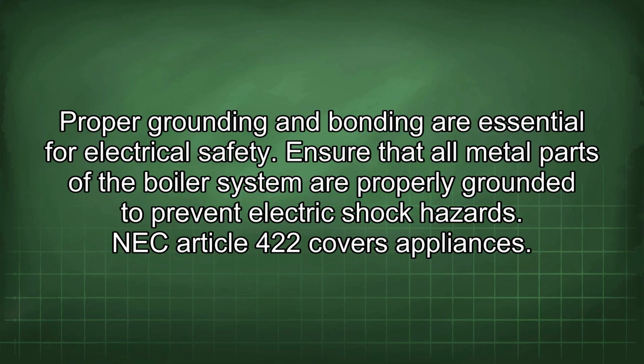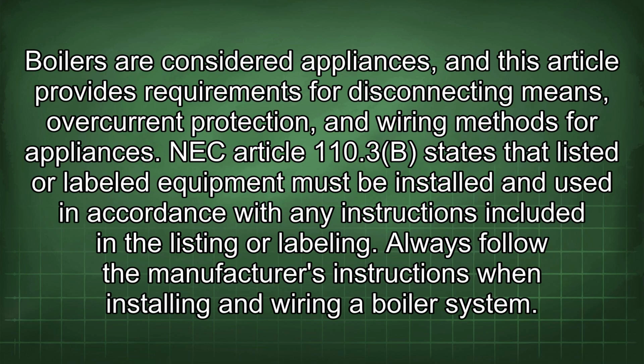NEC Article 422 covers appliances. Boilers are considered appliances, and this article provides requirements for disconnecting means, overcurrent protection, and wiring methods for appliances. NEC Article 110.3(B) states that listed or labeled equipment must be installed and used in accordance with any instructions included in the listing or labeling. Always follow the manufacturer's instructions when installing and wiring a boiler system.